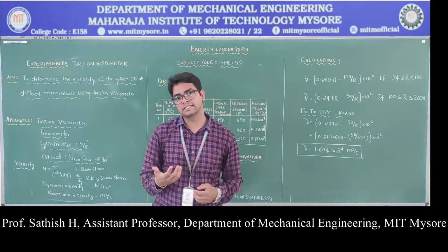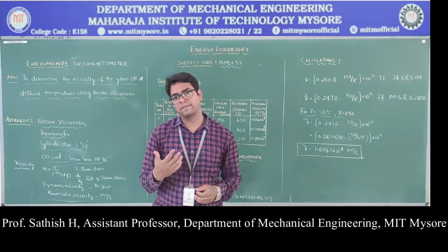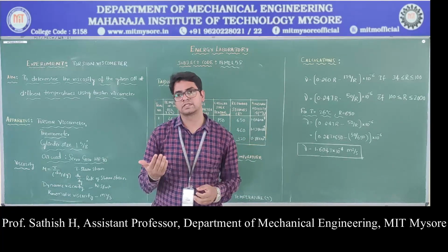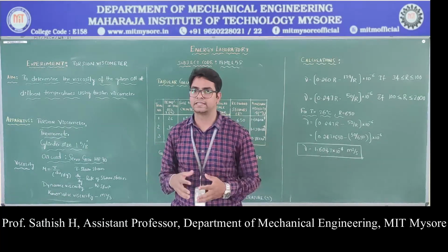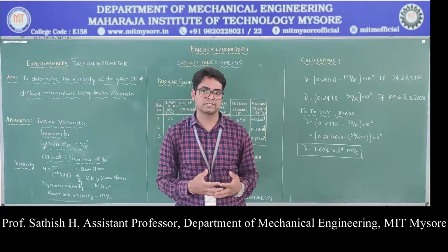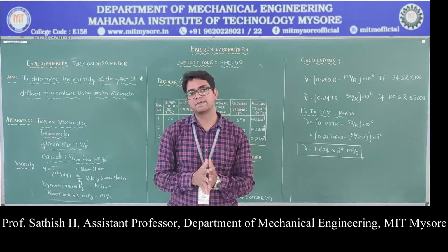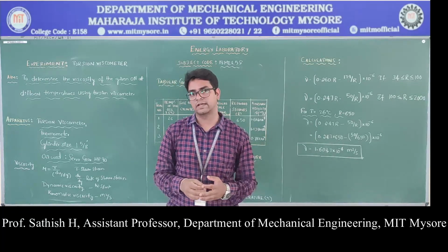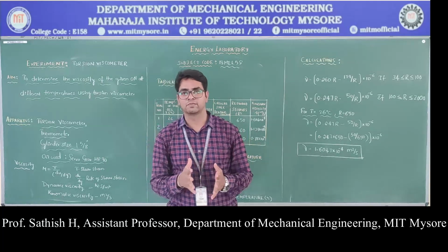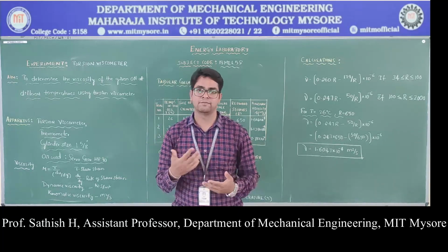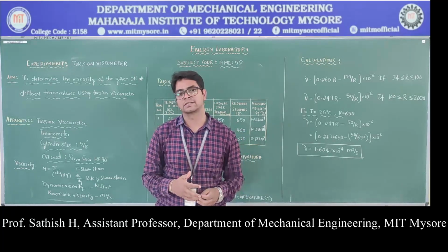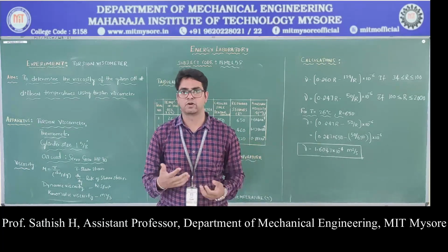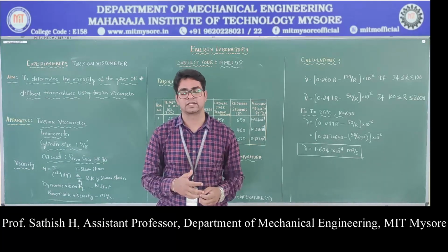If the viscosity is less, the important function of the fluid as a lubricating oil suffers. If the viscosity reduces, the lubricating capability of that oil will reduce, rubbing of the moving parts will happen, and wear might take place. Also, less viscosity can cause leakage of the fluid, both internal and external leakages.